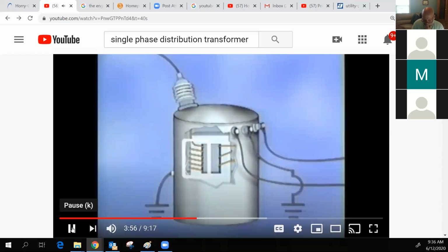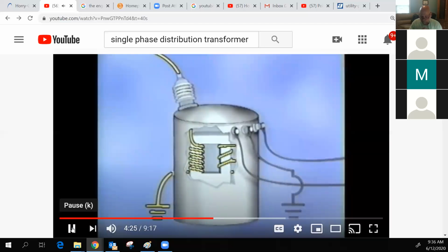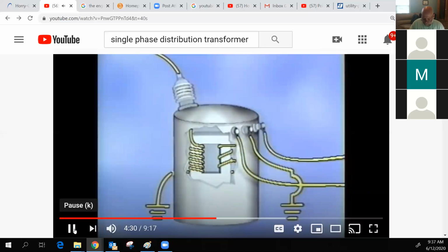The primary winding in this transformer is supplied with primary distribution voltage from a distribution line on the poles. Primary voltage is applied through this lead that runs through the primary bushing to one end of the primary winding. The other end of the winding is tied to the transformer's housing, and an external ground is applied. The secondary, or utilization voltage induced in the secondary winding, is tapped off the transformer through leads that pass through the secondary bushings on the side of the housing.